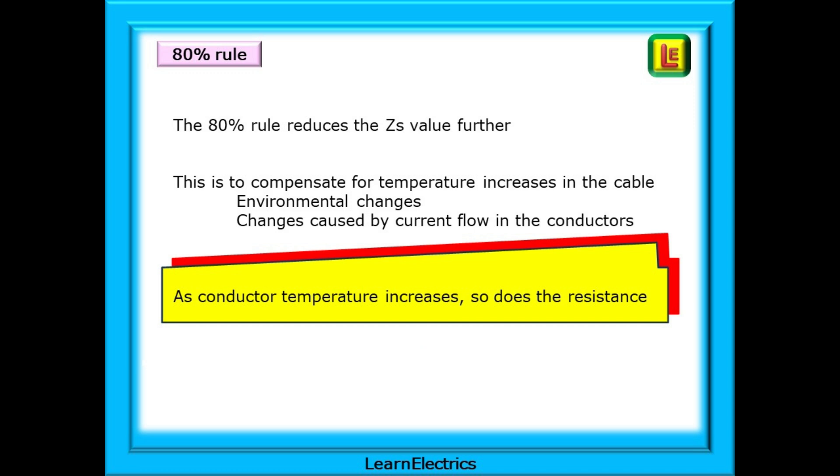This is because of an adjustment that we make and we call this adjustment the 80% rule. The 80% rule reduces the ZS value even further. This is to compensate for temperature increases in the cable such as environmental changes, grouping of cables or changes caused by current flow in the conductors. As the conductor temperature increases so does the resistance. If the resistance increases then the current goes the opposite way and decreases.